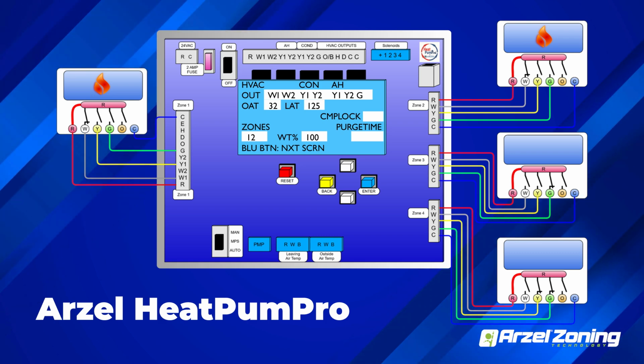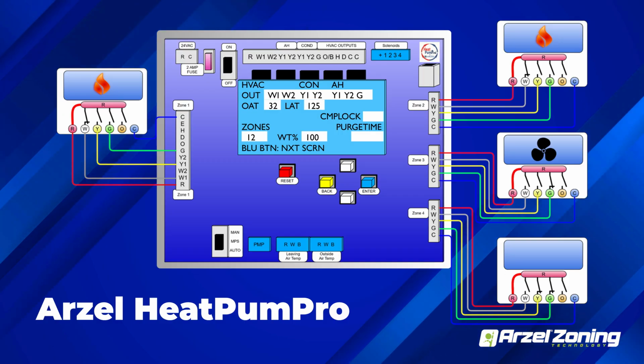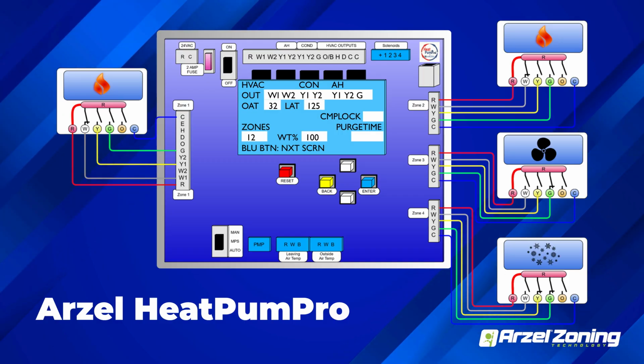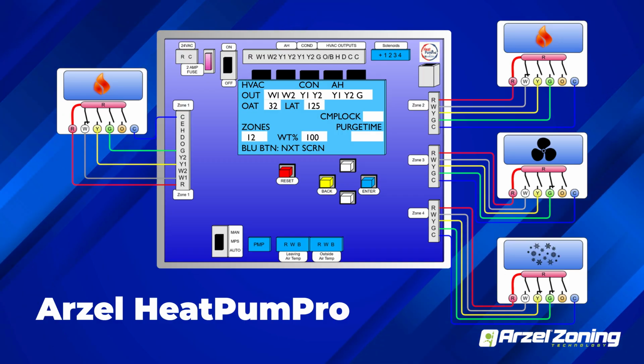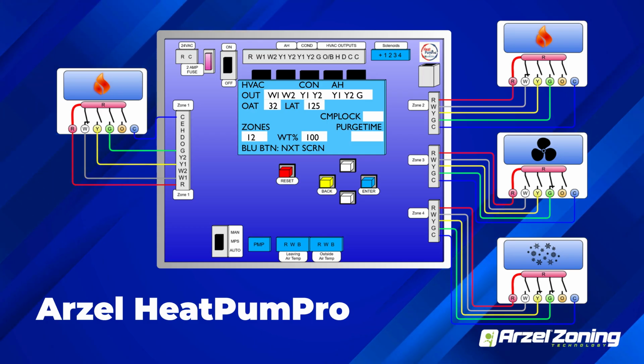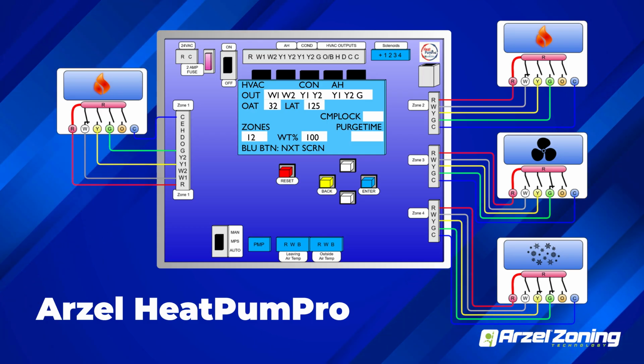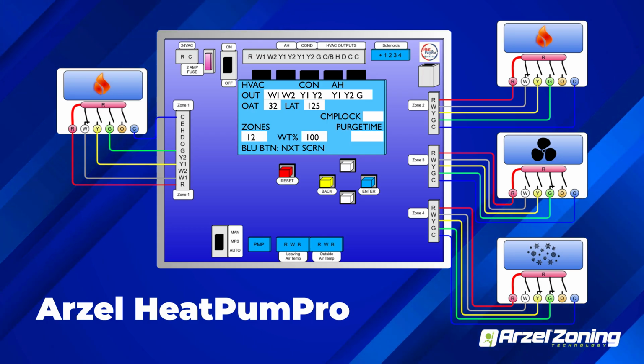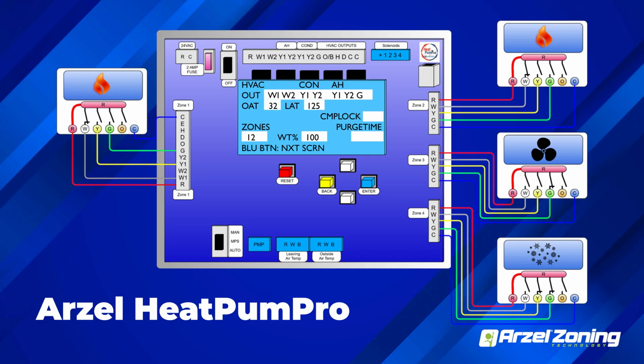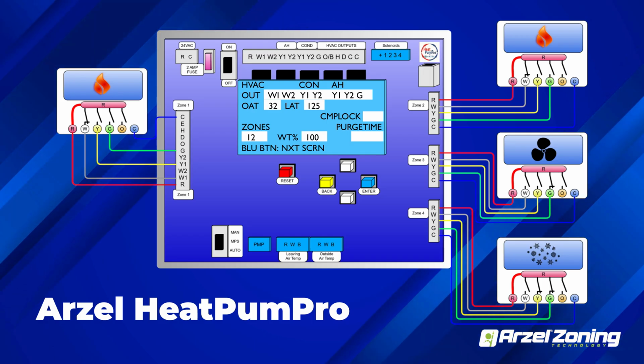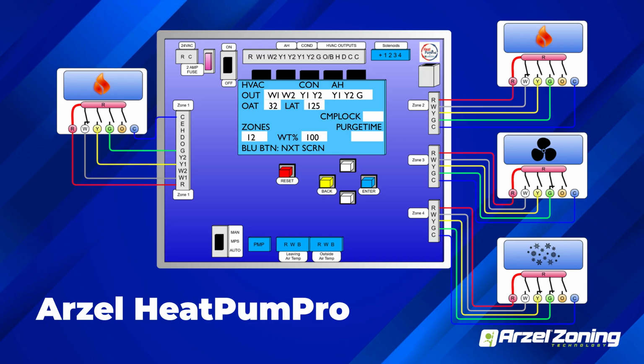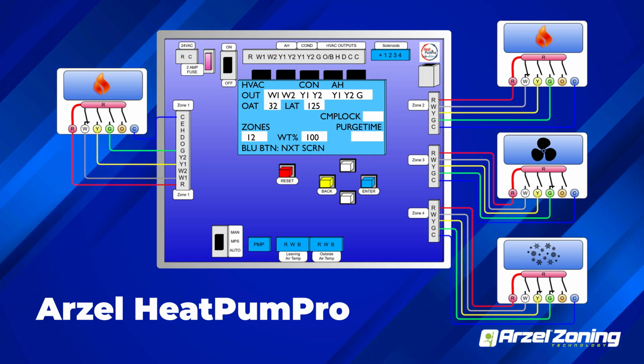So we can have thermostats all calling for different things: fan calls, heating calls, cooling calls. The Arzel panel applies a set of rules and determines what we're going to send to our equipment so that we aren't damaging our equipment with conflicting calls. When we look at the Arzel HeatPumPro, there's that line that says out. That line that says out tells you exactly what's going to your equipment.